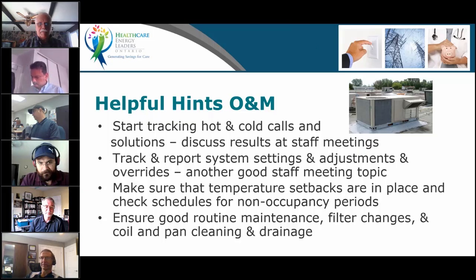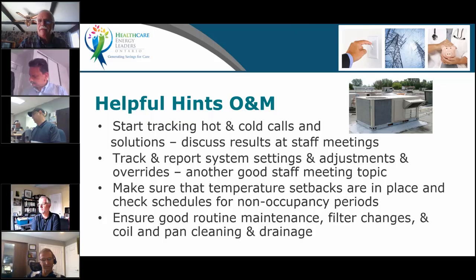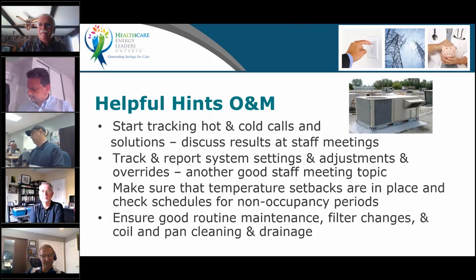So just in case anybody doubts, setbacks always save energy, but be very careful how you do it. A lot of hospitals can schedule systems for, like I said, type 2 spaces and type 3 spaces. They can be set back and they can be scheduled. You can shut off those sections. When it's a type 2 space, you have to monitor the space temperature so it stays within certain parameters, but it can be done and it should be done. I'm not talking about the COVID period. During COVID, there are specific ways of running the system.